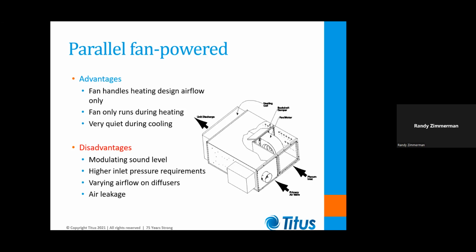The disadvantages would be the modulating sound level. That's one thing that some engineers don't like about parallel fan boxes. They've got multiple sound levels. There's one sound level at maximum cooling. There's one sound level at minimum cooling. And then the sound, of course, jumps up when that fan turns on. So you've got different sound levels to deal with. You've also got that higher inlet pressure requirement, like 1 or 1.5 inches, as opposed to the ½ inch you might be able to get away with on a series fan box.